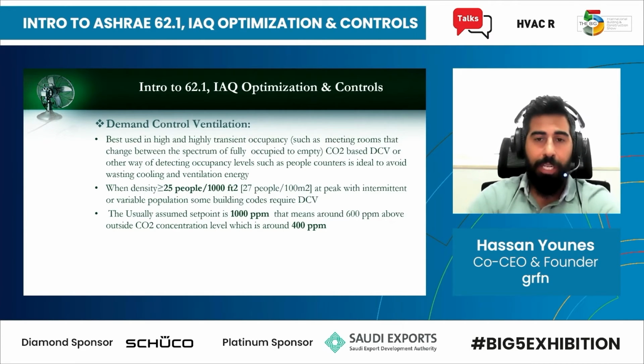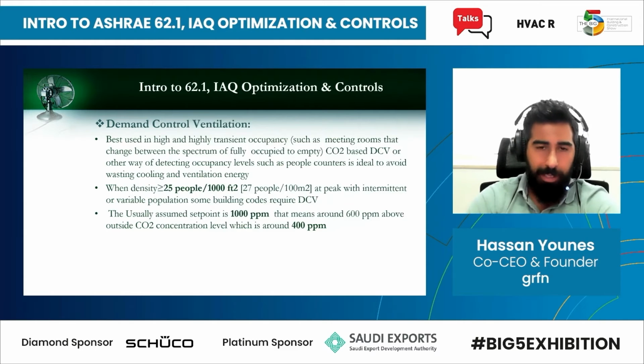Now, coming to demand control ventilation, it's normally used to reduce energy consumption when we don't need that amount of ventilation because we have lower occupancy at different points in time. If it's, let's say, an office building and the same number of people are there, demand control ventilation won't help. We can just turn off the machines when people leave the building and then turn them back on when they arrive. But if you have, let's say, a meeting room where sometimes it's 20 people in that room, sometimes it's only 2, we can take advantage of this varying outside air requirement. When we have only 2 people, we can just provide the required outside air for these 2 people, plus the area requirement, which remains constant.